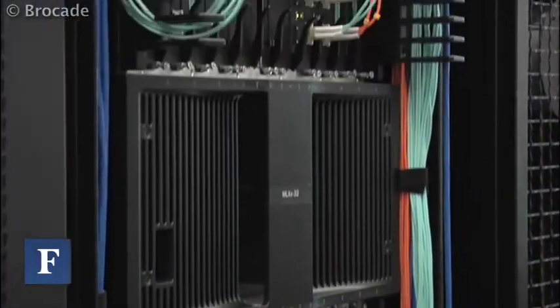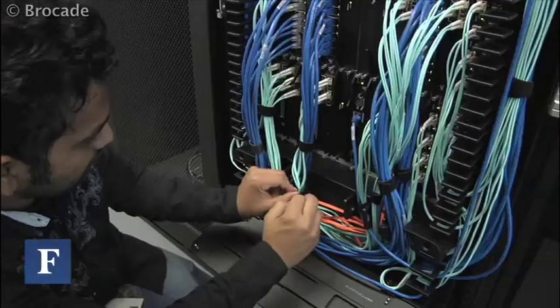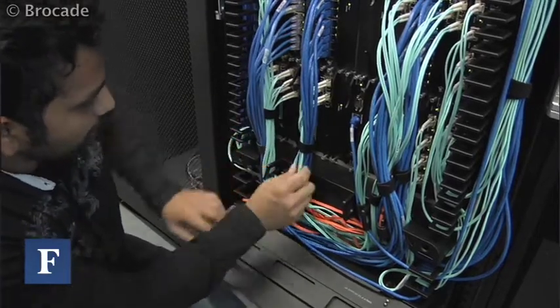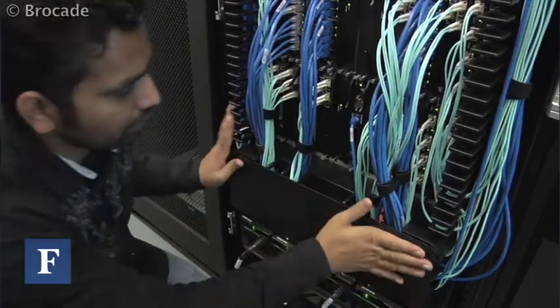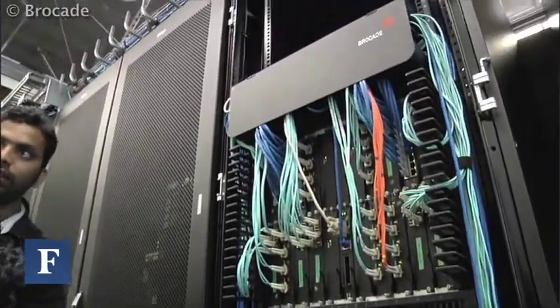We bring it all the way down inside the data center and then convert it to the voltages used by the equipment as close to the equipment as we can get it. That saves us 2 or 3% of the overall energy budget in the data center by converting very late in the stage, down in the data center.